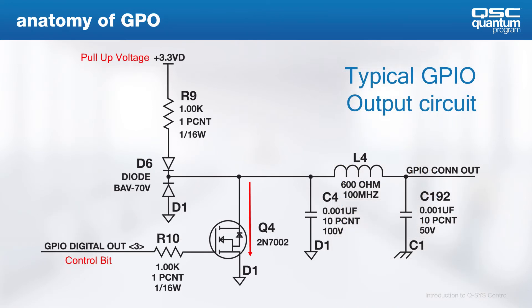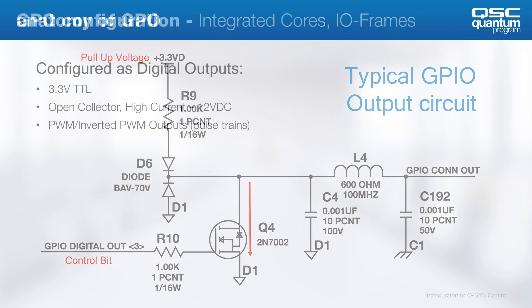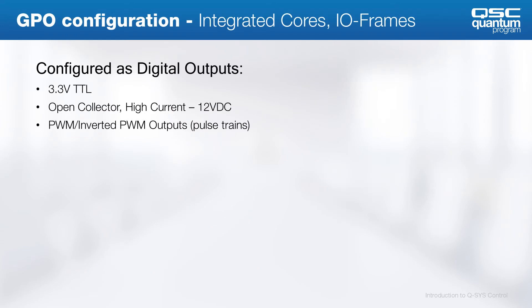Now let's look at the output side of GPIO. The anatomy of this circuit contains a transistor and some protection circuitry. If we toggle the control bit entering the circuit to be low, the transistor provides a sink to ground, which will provide a logic low on the output. If the control bit is driven high, the pull-up voltage will be present on the output, allowing the voltmeter on the connected external device to measure a logic high voltage. GPIO output configurations available include digital outputs of 3.3 volt TTL, open collector high current up to 12 volts DC, and pulse width modulated or PWM pulse train outputs.